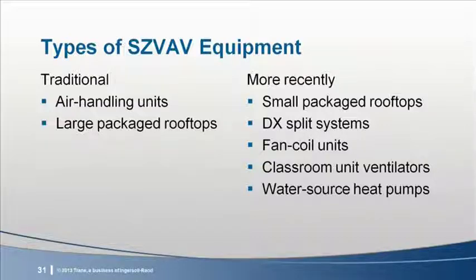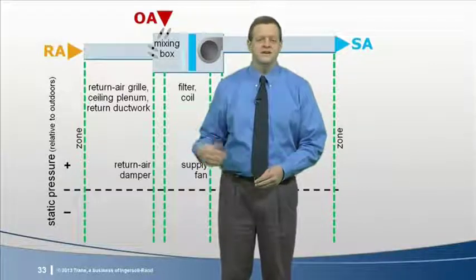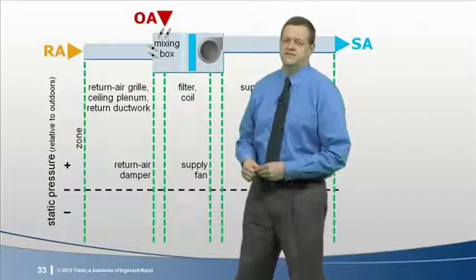Another aspect of air system control involves ensuring proper zone ventilation at all operating conditions. With a constant speed fan, ensuring proper ventilation is done by setting the position of the outdoor air damper during startup and balancing. Kind of a set it and forget it approach. But more and more, single-zone VAV is being used instead of traditional constant volume systems. With a variable speed fan, designers can no longer simply set it and forget it. John's going to explain. To demonstrate, let's look at this diagram of a simple single-zone VAV system.